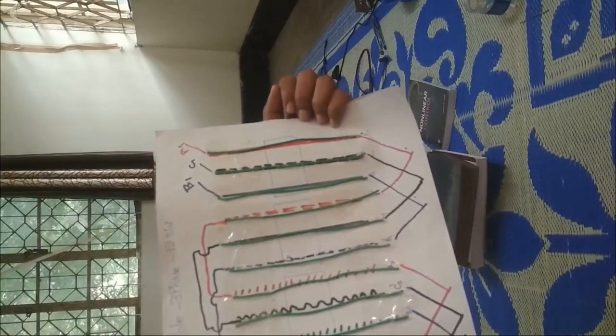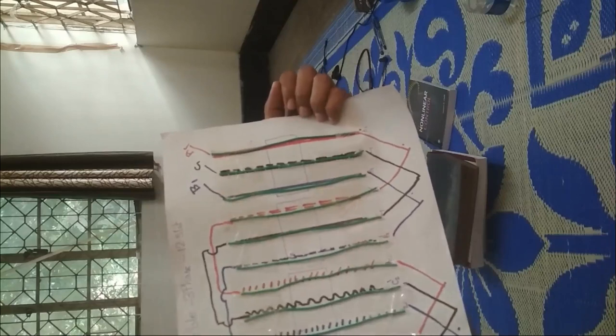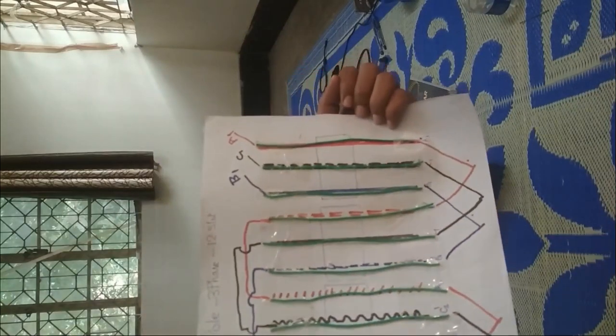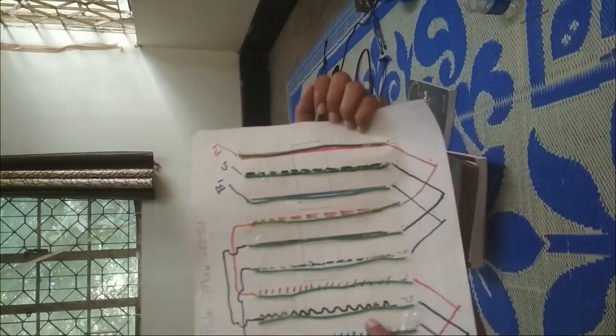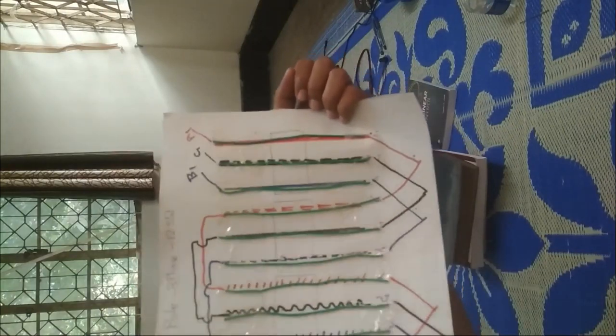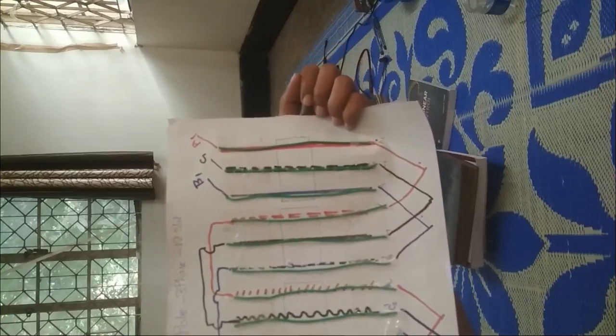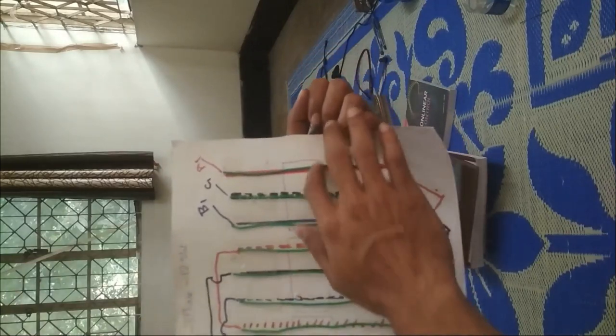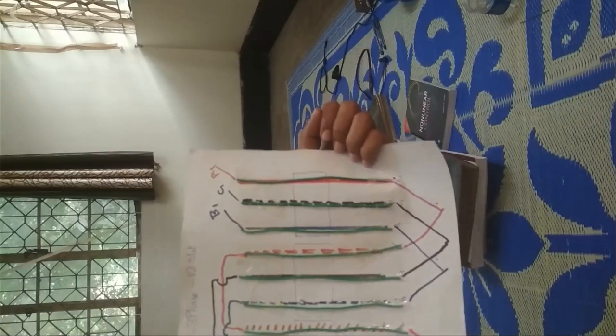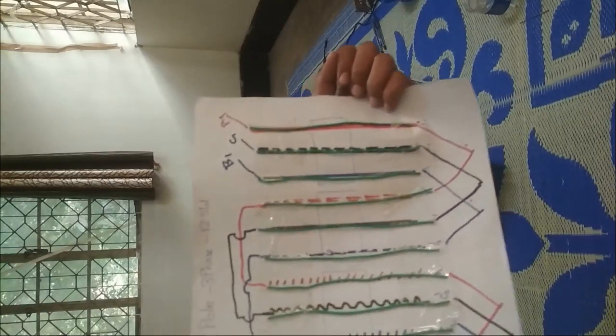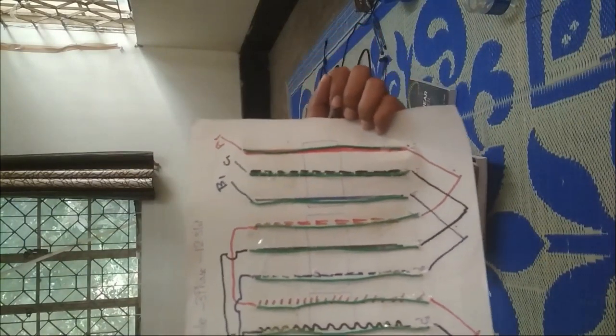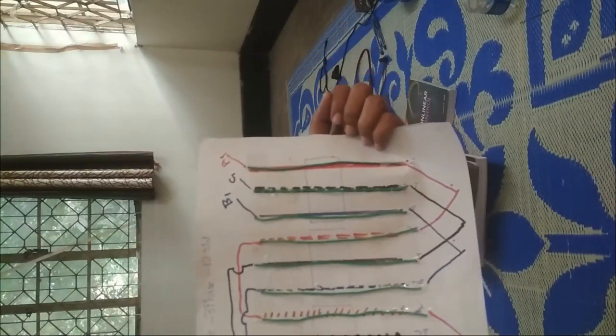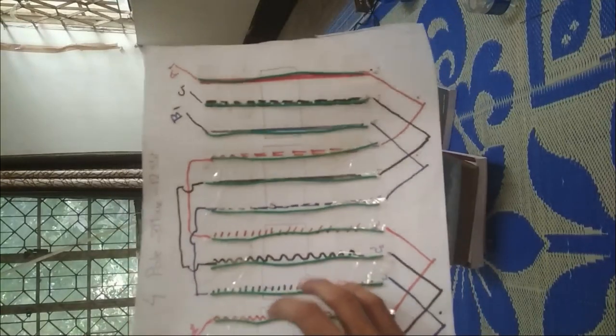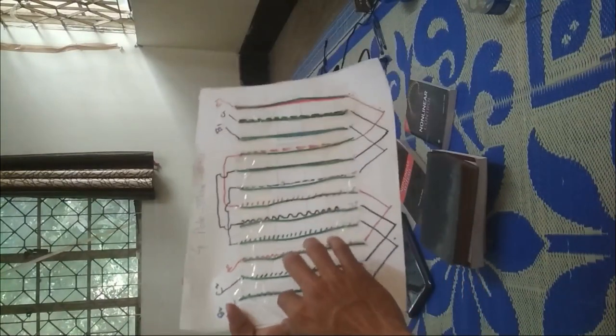First, we have to find out the slot angle. If we traverse from one end to the other along the lateral direction, the total electrical angle is 4 by 2 into 360, that is 720 degrees. So what is the angular span of an individual slot? Electrically, it is 720 by 12, that is 60 degrees. Mechanically, it is 360 by 12, that is 30 degrees. So these two are mechanically 30 degrees apart, and electrically 60 degrees apart.